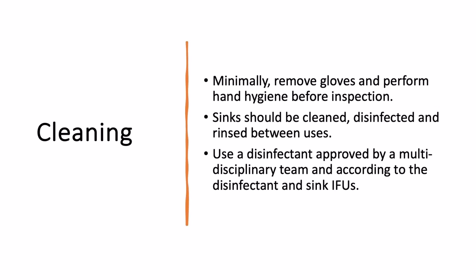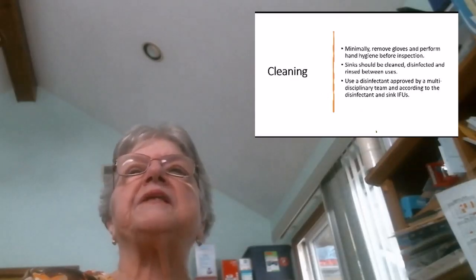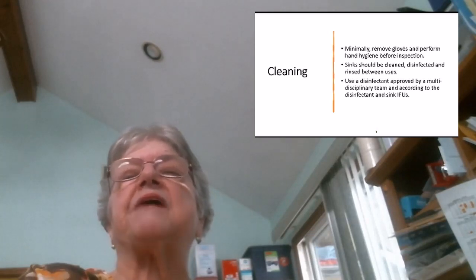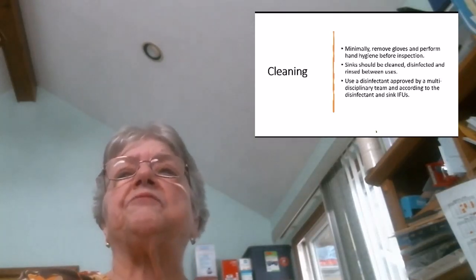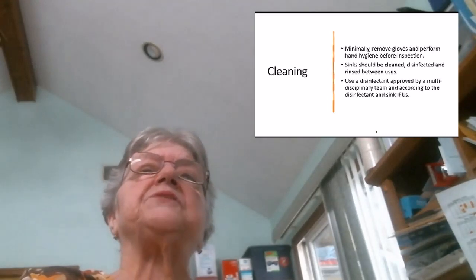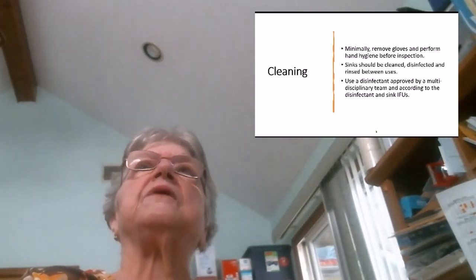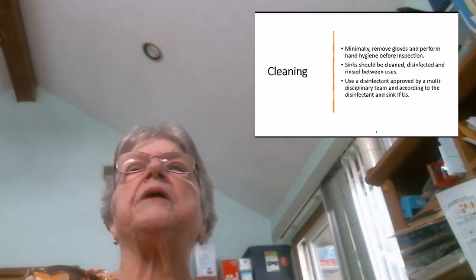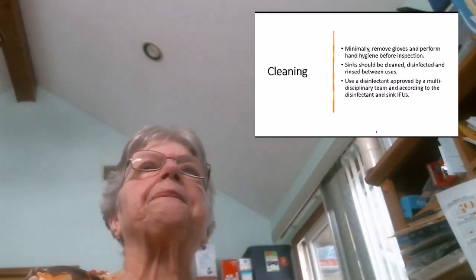When you clean, minimally remove your glove. After cleaning, minimally remove the gloves and perform hand hygiene before you inspect the scope. Sinks should be cleaned, disinfected, and rinsed between uses. You should use a disinfectant approved by a multidisciplinary team, and according to the disinfectant and sink IFUs. I've never seen a sink IFU with a recommendation, although they might tell you not to use bleach because it'll really harm your stainless steel, but you do want to disinfect your sinks.